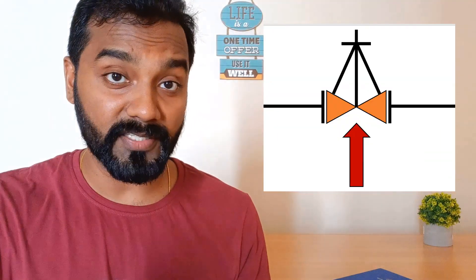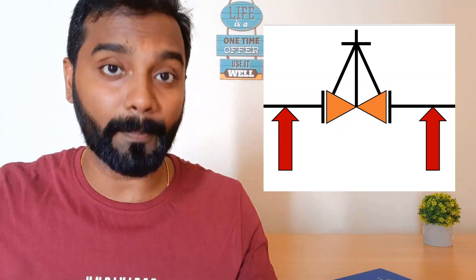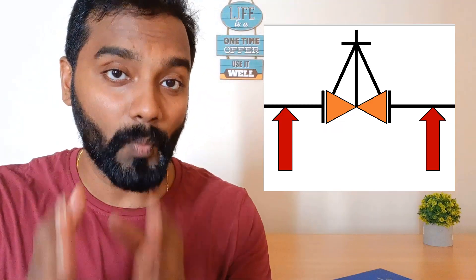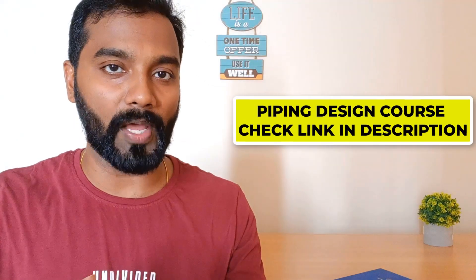That is one of the reasons why providing support directly below a valve is not recommended. The second reason is that the bottom profile of the valve is not suitable for supporting — it does not have the kind of flat, precise surface where a support can be properly provided. It is advisable to provide support over the piping so that the piping remains flexible and no additional loads act on the valve. If you provide support at the bottom of the valve, the valve will experience a difference in load from either side, which is not good for the valve body.